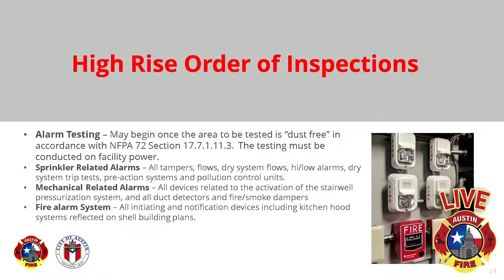The fire alarm system. Typically speaking, after the sprinkler-related alarms are completed, we'll do mechanical and alarms like smoke detectors per floor. So if you've got 3 fire smoke dampers on a floor, a smoke detector in the electrical room, and a duct detector on your AHU in the mechanical room, we'll test all 3 of those things at the same time. And then we'll go down, or whichever floor is the most finished is where we'll start, and we'll work up to floors that aren't finished. And when it gets too dirty, then we'll stop. So normally, that's the way it goes. So a lot more alarm testing.